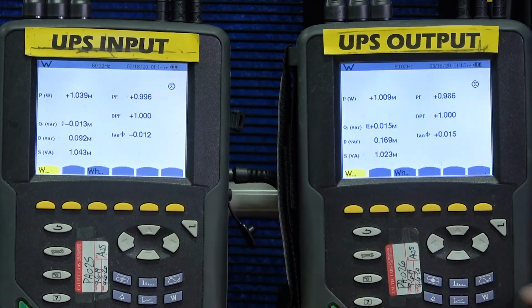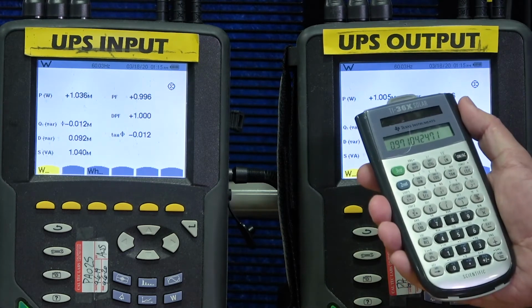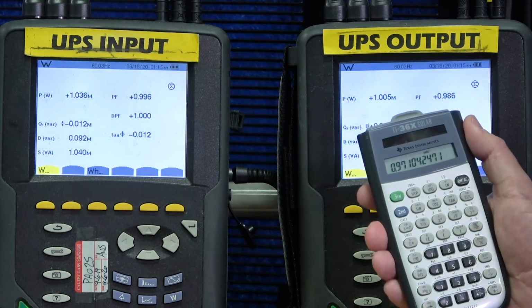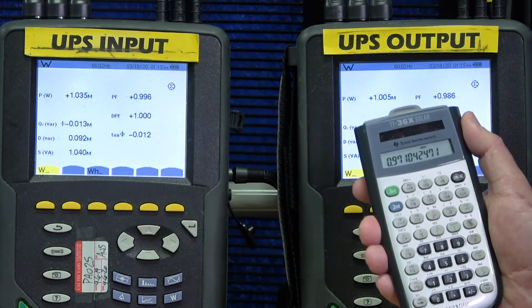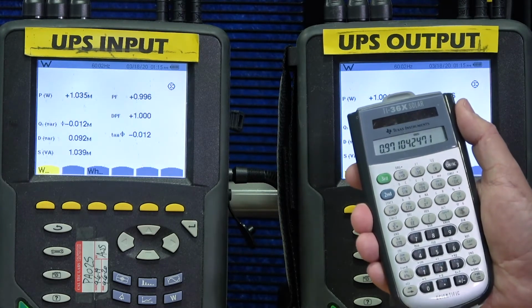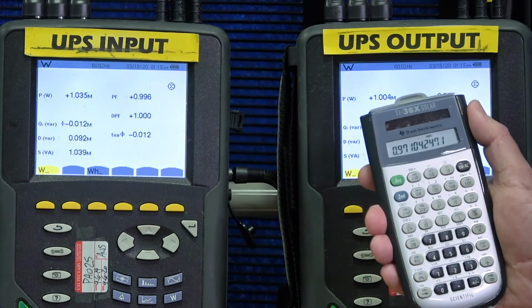Back to our input and output power here. We'll let this load stabilize a little bit. We can see we have 1.006 megawatts on the output divided by 1.036 megawatts on the input for a combined total of 97.1% UPS efficiency at 50% load.